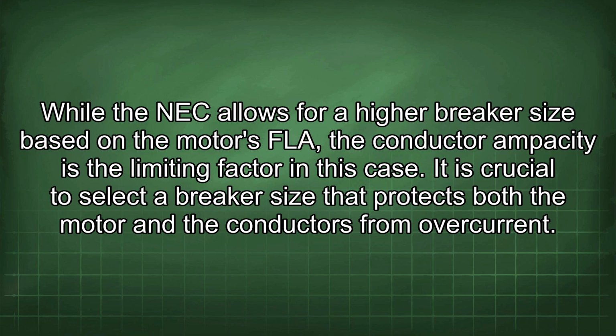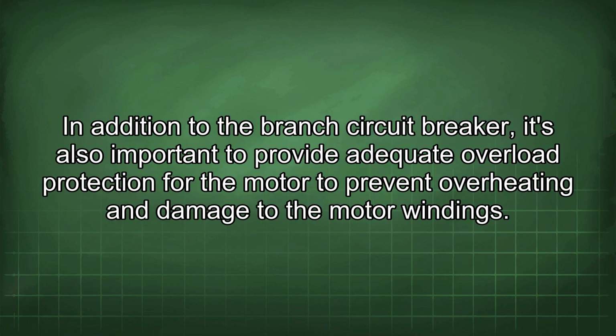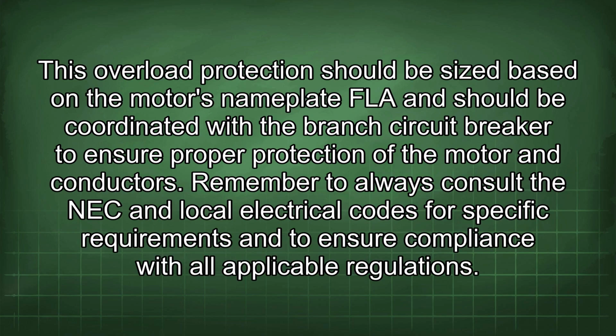It is crucial to select a breaker size that protects both the motor and the conductors from overcurrent. In addition to the branch circuit breaker, it's also important to provide adequate overload protection for the motor to prevent overheating and damage to the motor windings. This overload protection should be sized based on the motor's nameplate FLA and should be coordinated with the branch circuit breaker to ensure proper protection of the motor and conductors. Remember to always consult the NEC and local electrical codes for specific requirements and to ensure compliance with all applicable regulations.